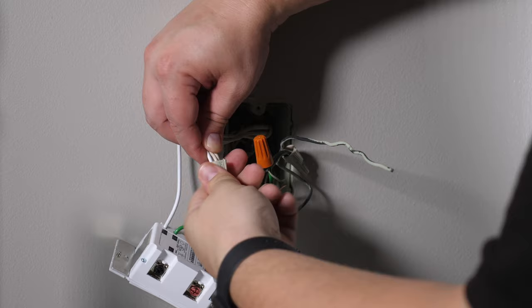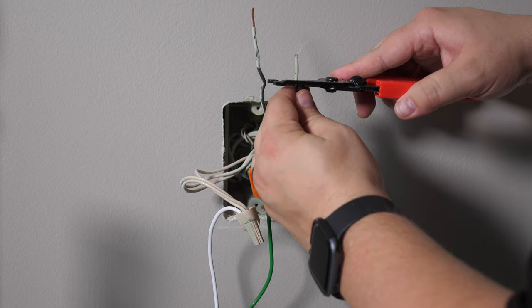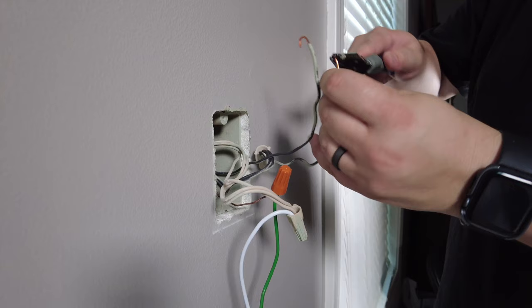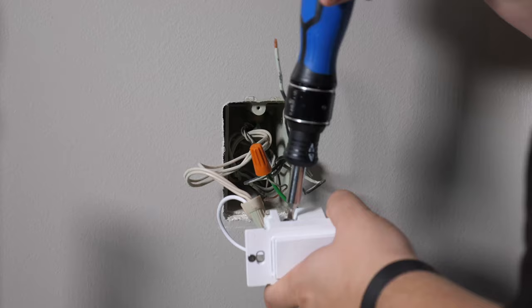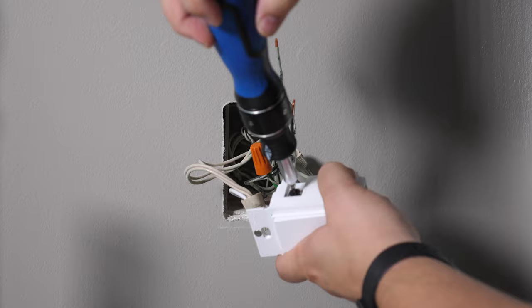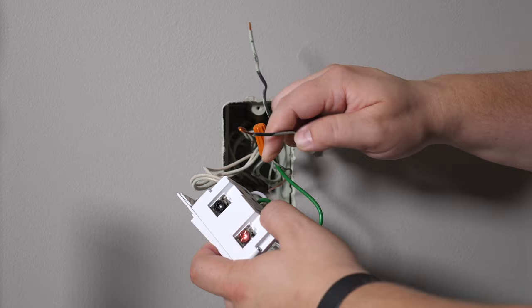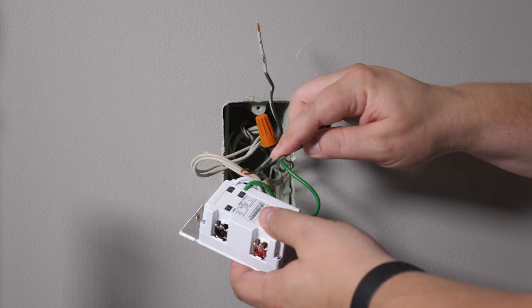Now we're going to strip off the wire that we need for both the line and the load terminals. I'm just going to form a nice little J hook with my pliers. Same with this one. We'll need to loosen up these side terminals here so we can hook this behind. We can either install it this way—side wire it with these terminals here—or it also includes a back wire method. Unlike the lights which we pulled out, it's not the stab-in type; it's actually the kind that you can put behind a clamp, which works really well.